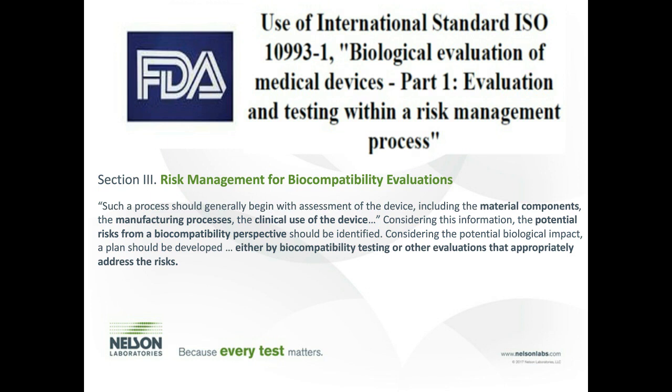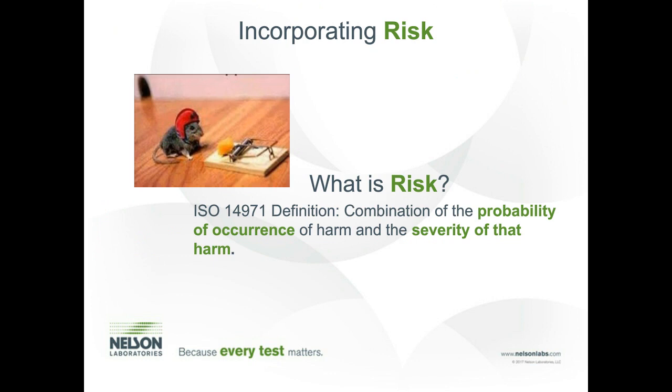So what is risk? I got this slide from a dear friend of mine, Dr. Rivardi. If you're not familiar with ISO 14971, this is another one, even though I don't consider reading any ISO document fun, it is something that I would recommend you spend some time getting to know, because the new ISO is going to rely highly on this document going forward. The definition of risk is the combination of the probability of occurrence of harm and the severity of that harm.